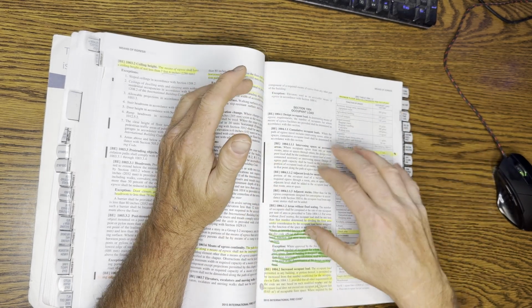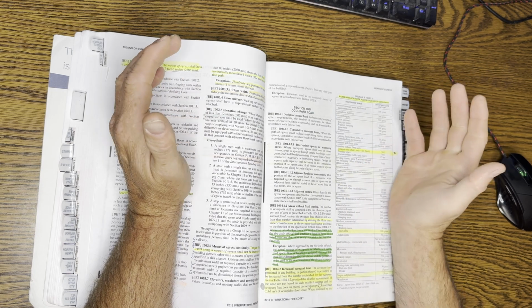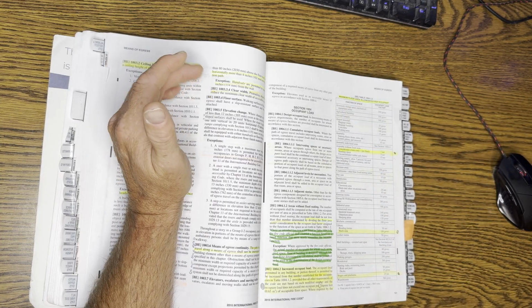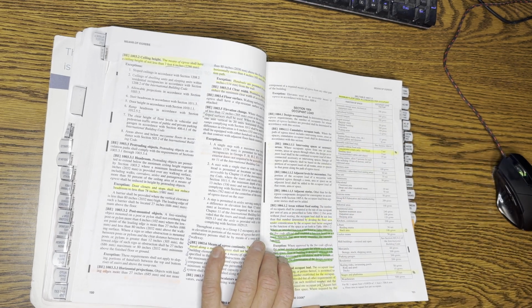Like a door, based on this code, a door for a sprinklered facility can allow 0.15 inch per person. So if I have a 32-inch clear width door, the reality is I can have like 210 people going through that door. That's your limiting factor, not so much this. But people get caught up on this. ICC expects you to understand that.